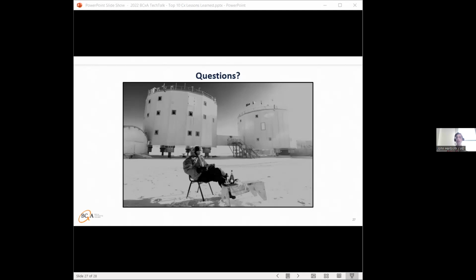In San Francisco, our city inspectors always reference NFPA. So when I look at drawings, I look at the location for access, and depending on the project, they might even have a lot more information on ceiling height and stuff like that. I'm always thinking about access to equipment. There's no code for access other than say NFPA for dampers, that you need at minimum 1 square foot of sized access hatch or removable duct.